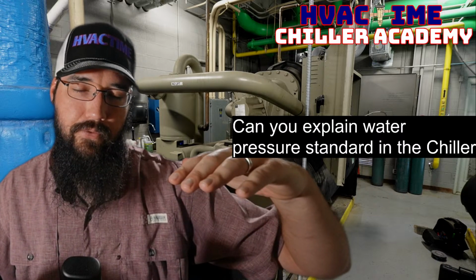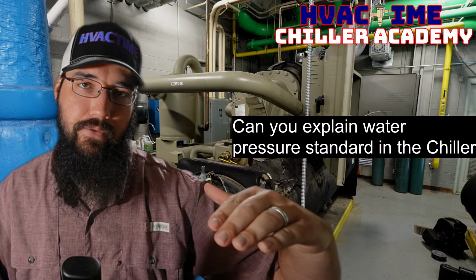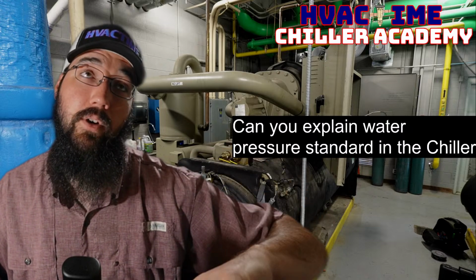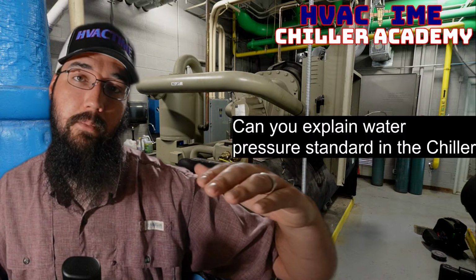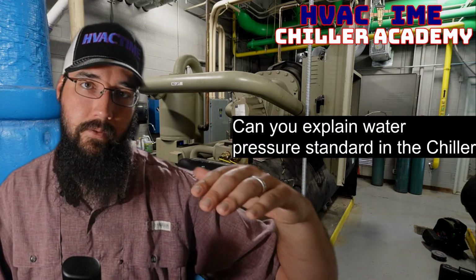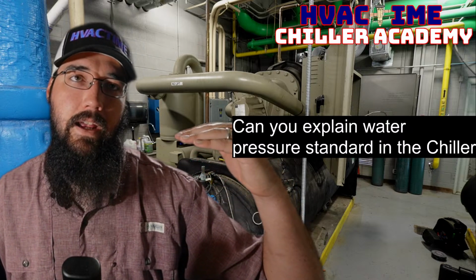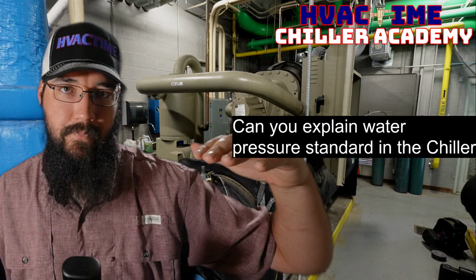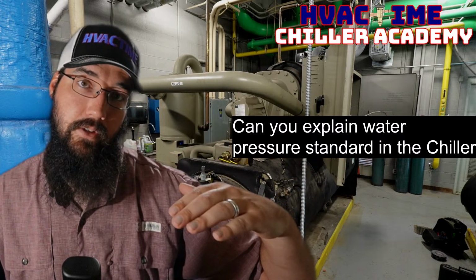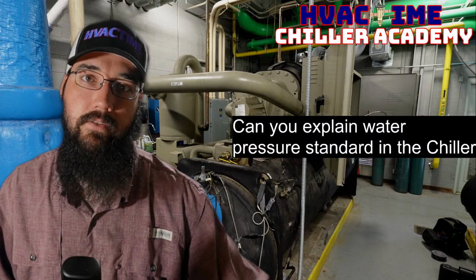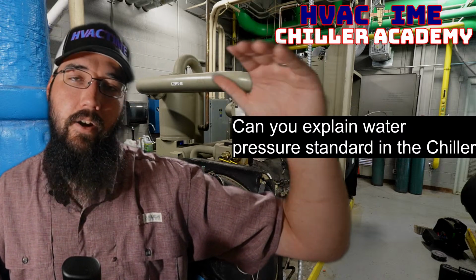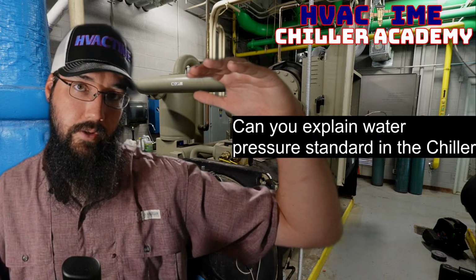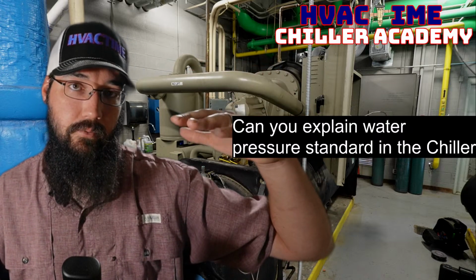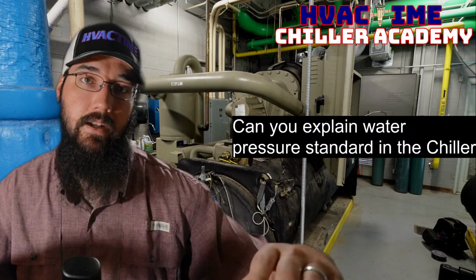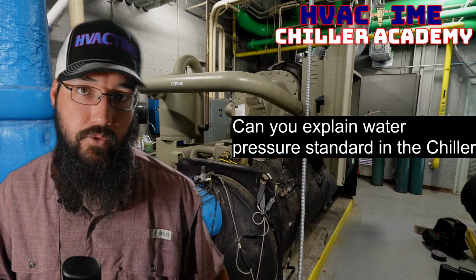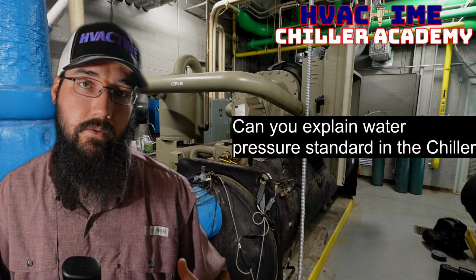for every 2.3 feet of elevation, you're going to have about 1 PSID. So you want to get to a neutral point, right? So if I've got a 10-story floor, and now a roof is counted as a story, right? So if you've got a chiller on the ground level and your air handlers are on the roof, then you've got a 2-story setup there, not a single story. Maybe just one single story on the main level, but you have to count that roof as an additional story when it comes to the calculations we're going to run.